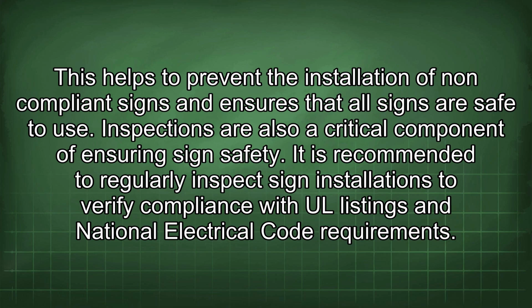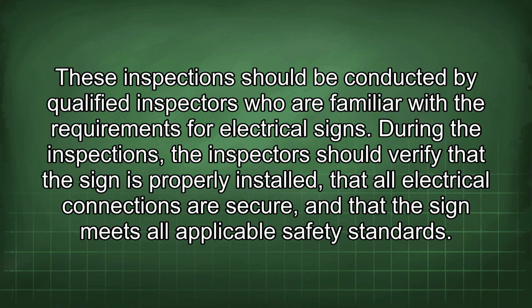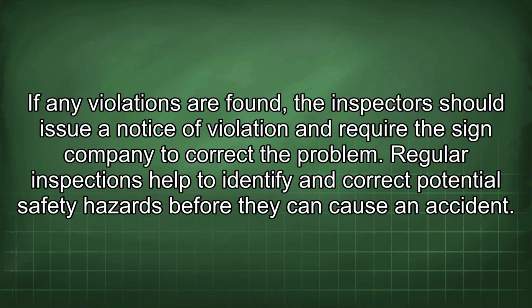Inspections are also a critical component of ensuring sign safety. It is recommended to regularly inspect sign installations to verify compliance with UL listings and National Electrical Code requirements. These inspections should be conducted by qualified inspectors who are familiar with the requirements for electrical signs. During the inspections, the inspector should verify that the sign is properly installed, that all electrical connections are secure, and that the sign meets all applicable safety standards. If any violations are found, the inspector should issue a notice of violation and require the sign company to correct the problem. Regular inspections help to identify and correct potential safety hazards before they can cause an accident.